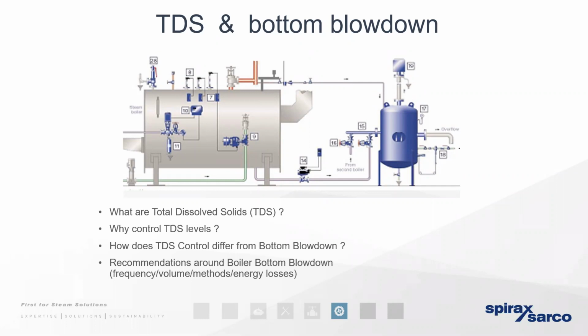So the good news is if we can recognize a manual blowdown valve, whether it be bottom blowdown or TDS, and encourage the steam user to move towards an automated blowdown control, then we can, in many cases, represent a significant payback. Now, boiler manufacturers, they will determine in their OEMs exactly how much blowdown should be performed. So we can quantify very, very easily if and when an over blowdown is being performed. We can determine what the energy loss is, and we can determine what the cost saving would be by moving from manual controls towards automated controls. And in many cases, we can be talking about a payback within months, if not, well, certainly sub 12 months.